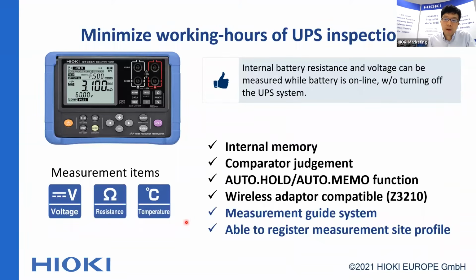These parameters can be measured while the UPS is online, and it can judge the battery conditions using the comparator function. These results are automatically stored in the internal memory. The test operator does not need to touch any keys during the test.